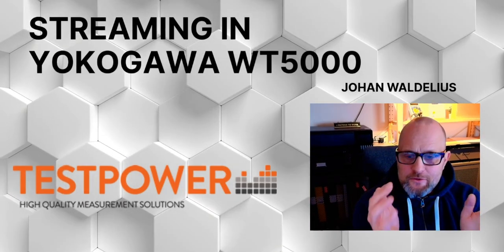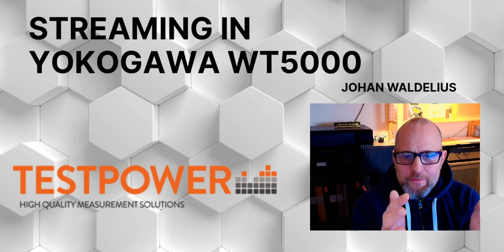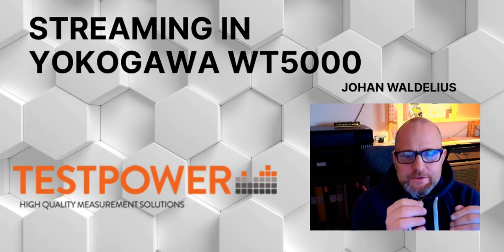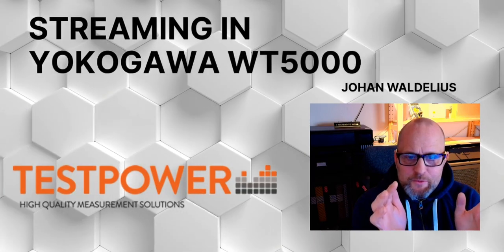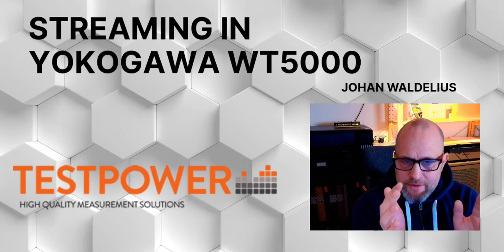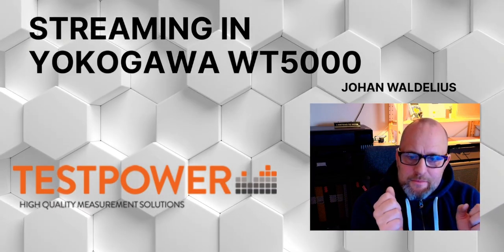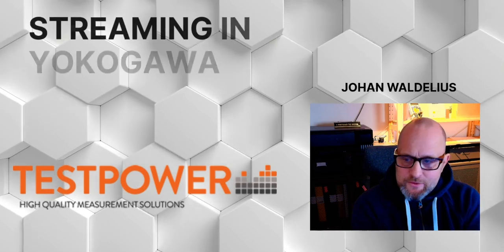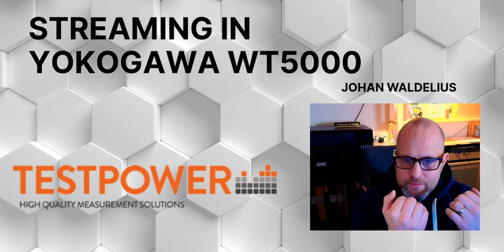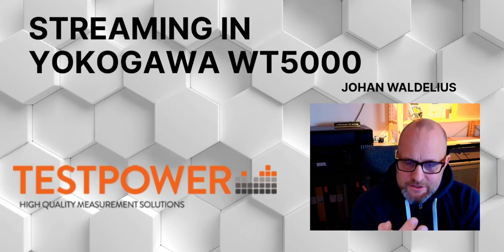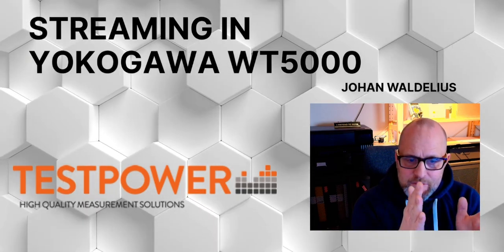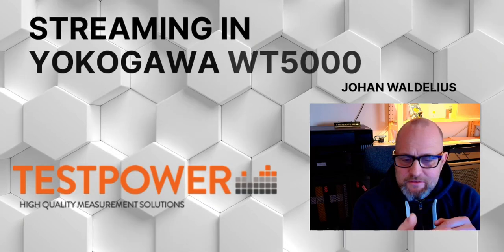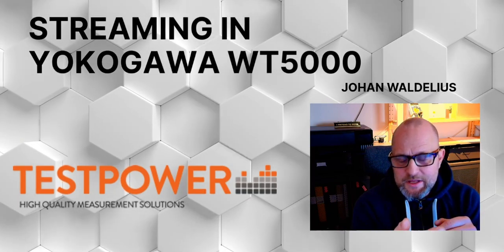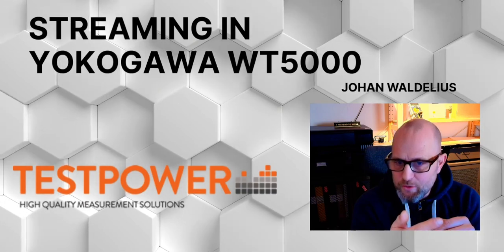Let's say you want to stream data from your power analyzer. For that, the WT5000 is equipped with an option called data streaming. This can be streamed directly from the power analyzer into your PC with up to 2 megasamples of data, and you can get up to 7 currents, 7 voltages, and the speed and torque signals from dual motors.